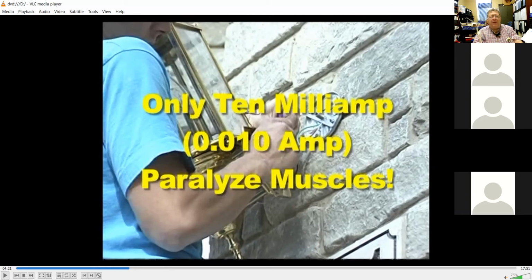Now, in the case of having some leakage current, if I had 3 amps going out of the hot wire to a hair dryer and 2.5 coming back, here's what the GFCI sees. Inside, when you run the two wires through the GFCI like that, it will say 3 amps minus 2.5 amps, and it sees a difference of how much?